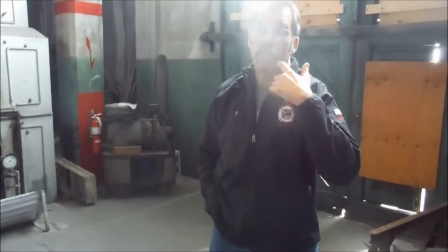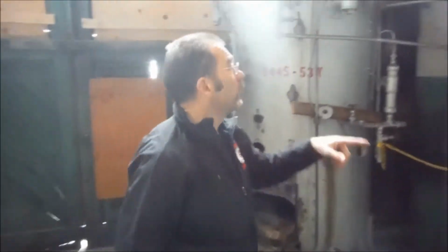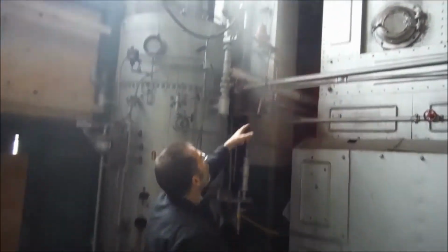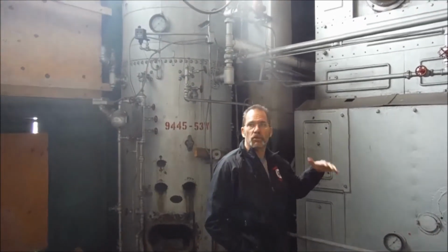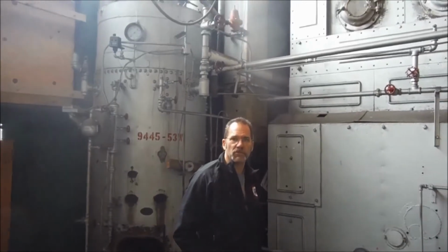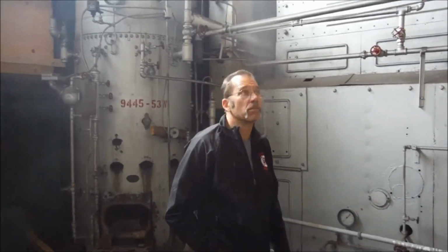But when you shut down a boiler like this, you can't just depressurize it and leave water in it. Right. Because it's iron, it's going to rust. It's also potentially going to freeze around here. So we would, in the Navy, pump steam from the operational boiler into the shutdown boilers to keep a certain amount of temperature and pressure, called a steam blanket layup. And I'll bet the reason that there's steam lines from this that go around the plant a little bit would be when you shut down the plant to be able to have steam to put the boilers in the proper layup. Makes sense.